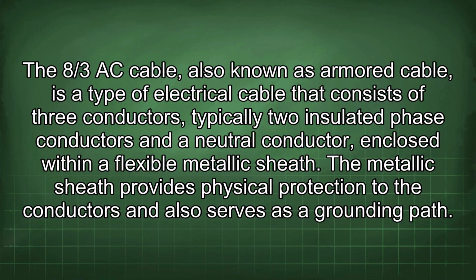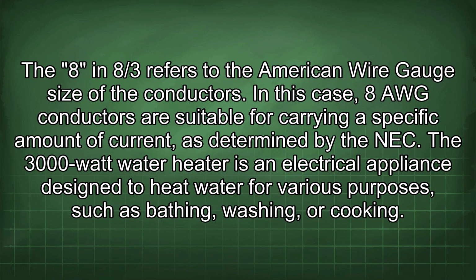The 8/3 AC cable, also known as armored cable, is a type of electrical cable that consists of three conductors, typically two insulated phase conductors and a neutral conductor, enclosed within a flexible metallic sheath. The metallic sheath provides physical protection to the conductors and also serves as a grounding path. The 8 in 8/3 refers to the American wire gauge size of the conductors. In this case, 8 AWG conductors are suitable for carrying a specific amount of current, as determined by the NEC.